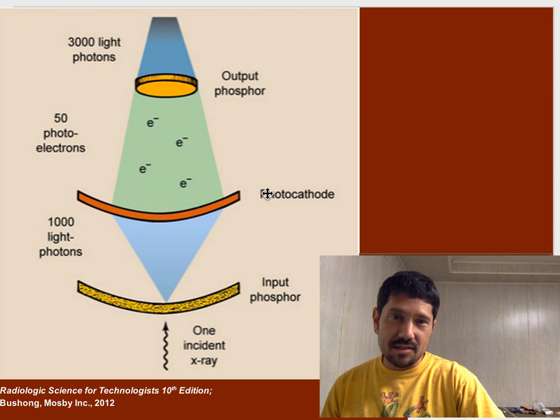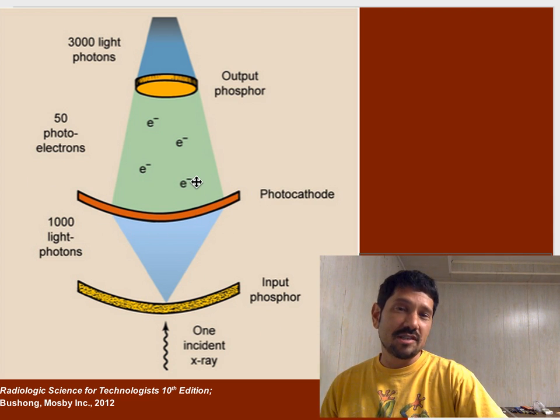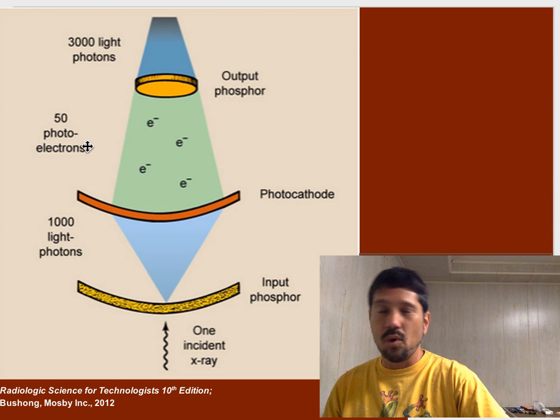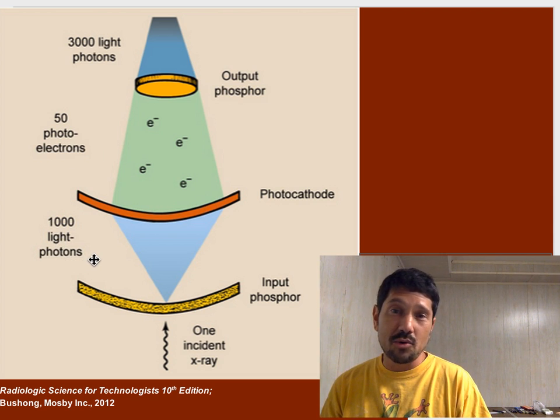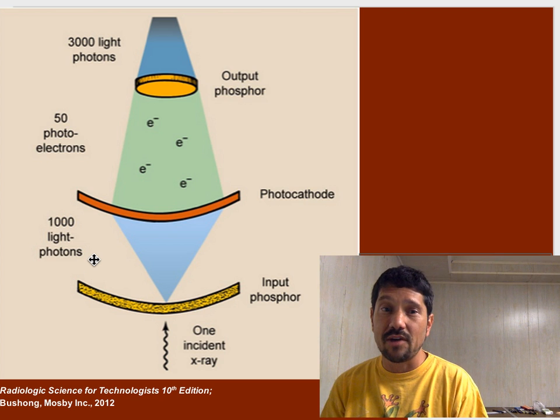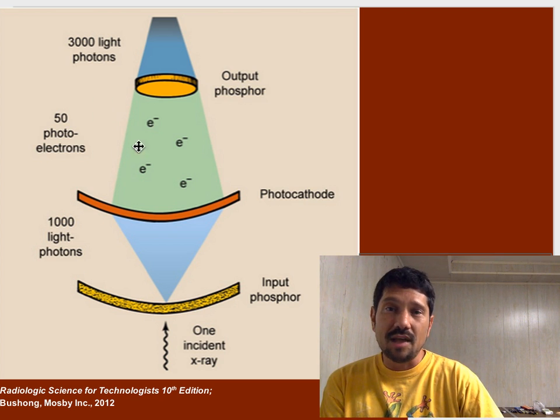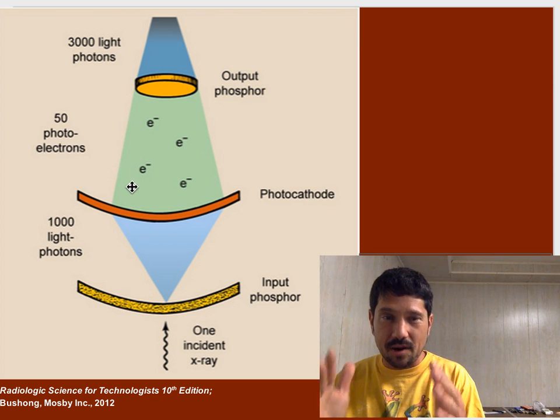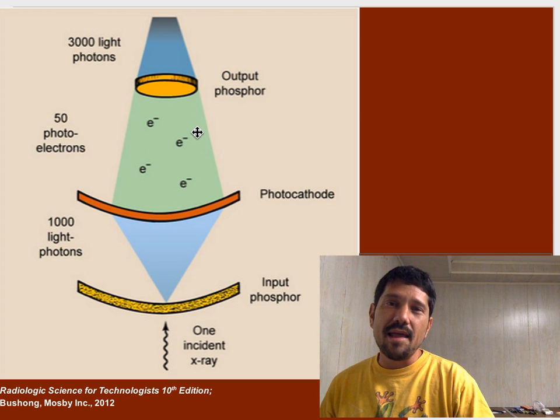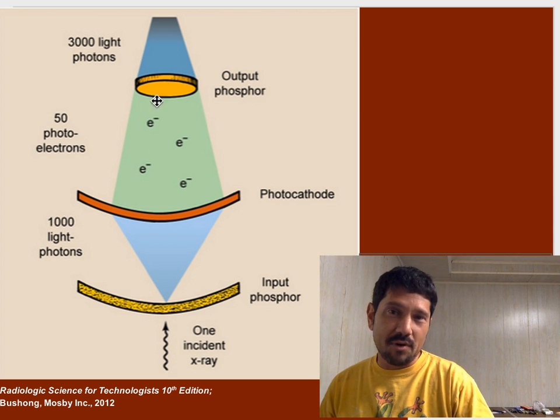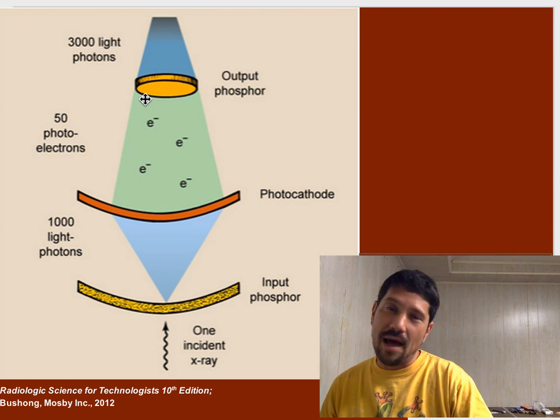That light then hits our photocathode, which it turns into electrons. And you don't get one electron for every one light photon. It takes quite a few light photons to generate each electron. Those electrons fly along and they get focused by our electrostatic lenses and they get minified. They get focused down onto a smaller output phosphor.